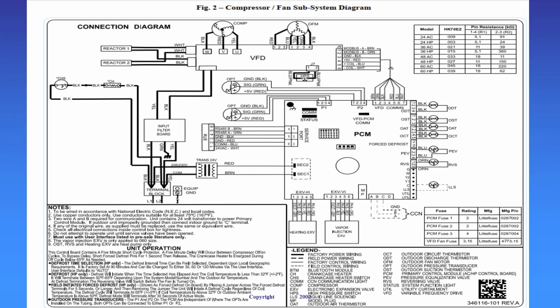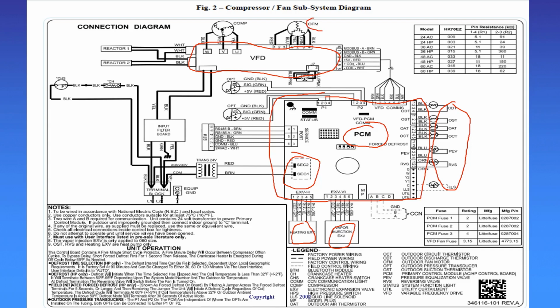This is a diagram of a current inverter product. And again, you'll notice that you have your circuit board and all of your components, your safety switches, reversing valve, various things plug into the circuit board. Your transformer plugs into the circuit board, your EXVs. So everything plugs into the circuit board and is controlled by the circuit board. Then of course you have your VFD board and your outdoor fan motor, and your compressor is plugged into the VFD board and is operated off of that.